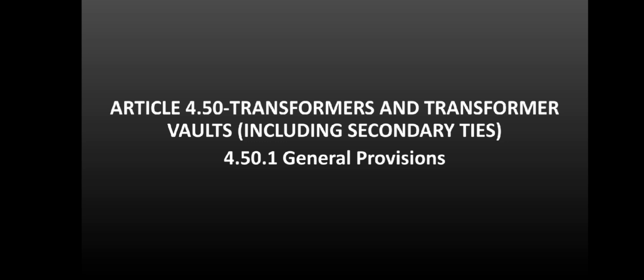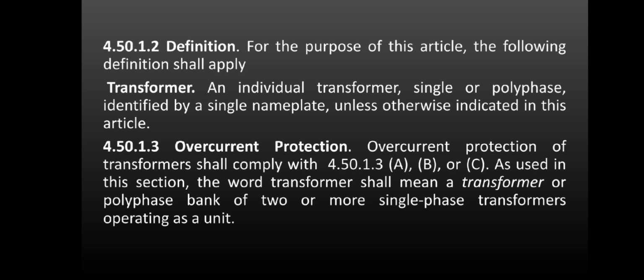4.50.1 General provision. Definition. For the purpose of this article, the following definition shall apply. Transformer: an individual transformer, single or polyphase, identified by a single nameplate unless otherwise indicated in this article. Overcurrent protection. Overcurrent protection of transformers shall comply with 4.50.1.3 A, B, or C as used in this section. The word transformer shall mean the transformer or polyphase bank of two or more single-phase transformers operating as a unit.